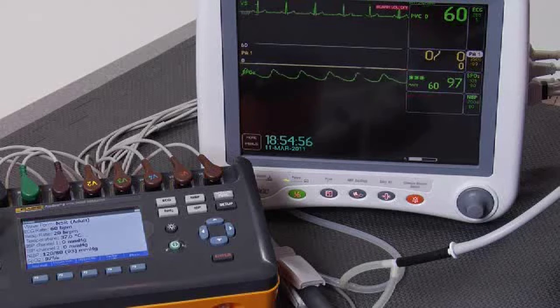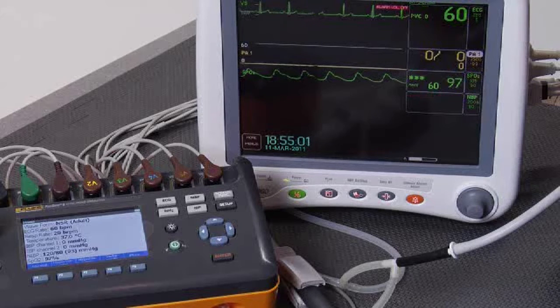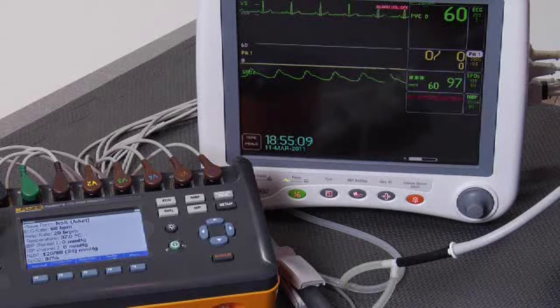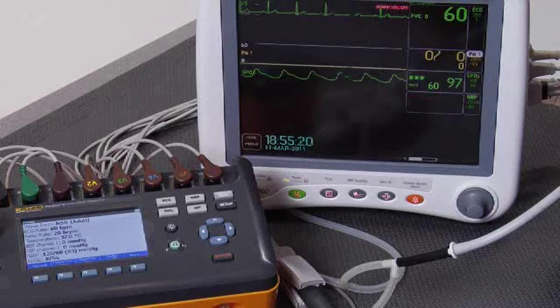The parameters we're going to test are ECG rate, respiratory rate, invasive blood pressure channel 1. We're going to do a cuff blood pressure and IBP measurement and oximetry. We're going to try and get all of this testing done in under 5 minutes. As you can see, there's a digital clock shown in the lower left-hand corner of the patient monitor display, so you can be your own judge as to whether we can get through this test within 5 minutes or not.